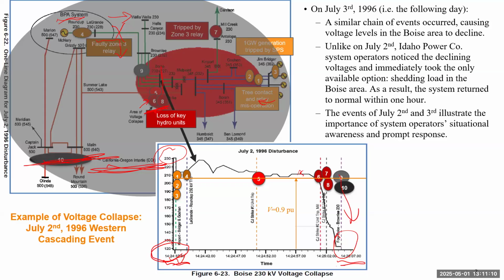Okay, so if you're an operator, and you have the operating guys saying this system needs to operate way above 90%, 0.9, and you use that threshold, and whenever the voltage drops you take action, that's too late. Which means there must be some mechanism behind this phenomenon, showing when the voltage instability can become very likely on your system. Then you need to take some early action. That's what we want to answer in this section.